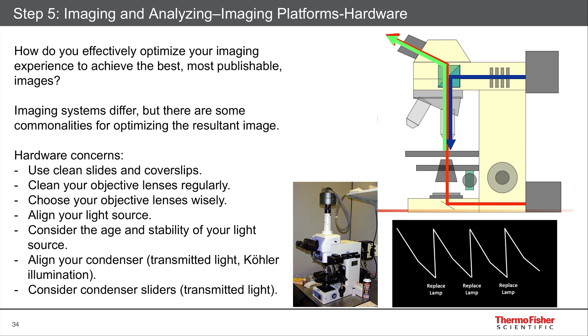Here's an example of a traditional microscope. The blue line shows excitation light for fluorescence traveling from the mercury bulb, bouncing off the dichroic mirror in the filter cube, and then down through the objective to the sample on the stage. The dye then emits at a higher wavelength — shown in the green line — which goes back up through the filter set to your eyes or camera. The red line represents transmitted light from a tungsten bulb that passes up through the condenser, through the sample, and up to your eyes or camera. There's also a picture of a Nikon scope at the bottom as an example.